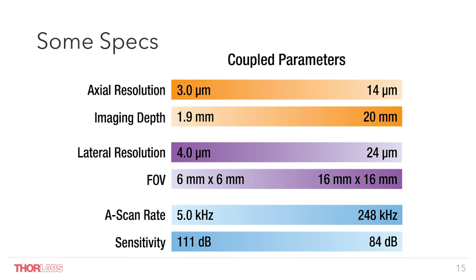Now one last word on the general specs of an OCT system, as there exist three major intercoupled parameter pairs. The axial resolution depends on the spectral characteristics of the light source — the broader the better — and for shorter wavelengths the axial resolution is also better. However, when using a finite element detection unit like a spectrometer with a 2048-pixel line scan camera, we face a limit in imaging depth, and to comply with Nyquist, the imaging depth has to be counterbalanced with axial resolution. In short, high axial resolution systems have a shallow imaging depth, and if a longer imaging depth is needed, we have to compromise on resolution.